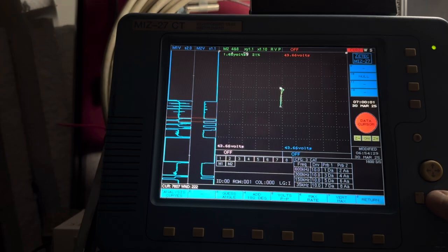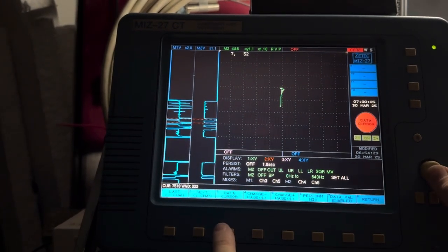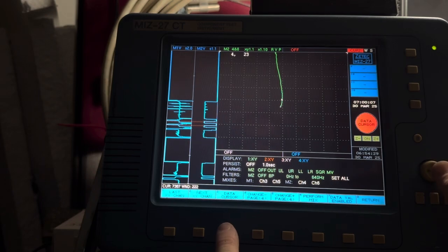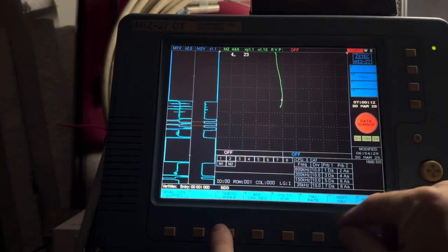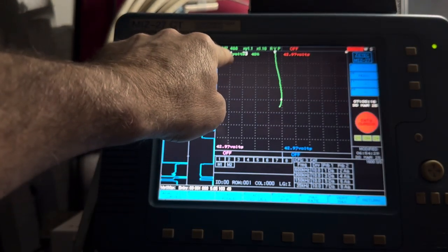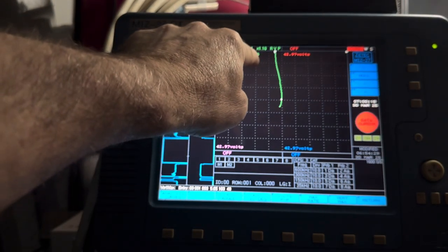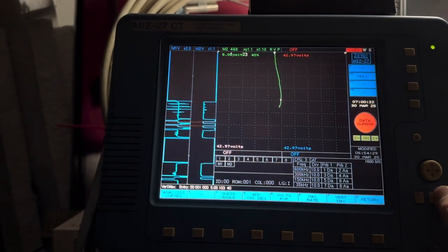Watch what happens to the amplitude when I go to the 40% wear scar. It's much bigger. So now when I go to measure and hit vert max, 5 volts, so it went from 1 point something volts to 5 volts. This is reading 40%.